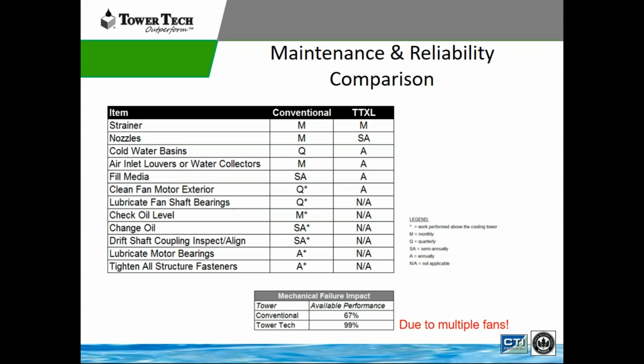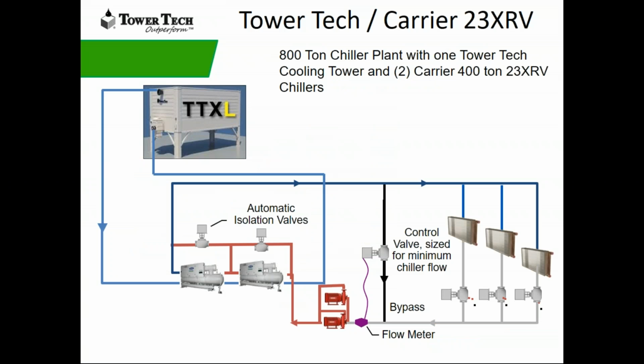They have this whole entire other line of things. Lubricate fan shaft bearings, check oil, change oil. Those are all part of a traditional tower system. And that's not free to an owner. That actually costs money. So when we look at this system, we're able to save on the maintenance side of it. But because of the redundancy of the multiple fans, on a conventional tower in that last example we gave you, if one tower failed, we only had 67% capacity available. Okay, on the TowerTech solution that we just showed you, if one fan failed, we had 99% available performance in that system.